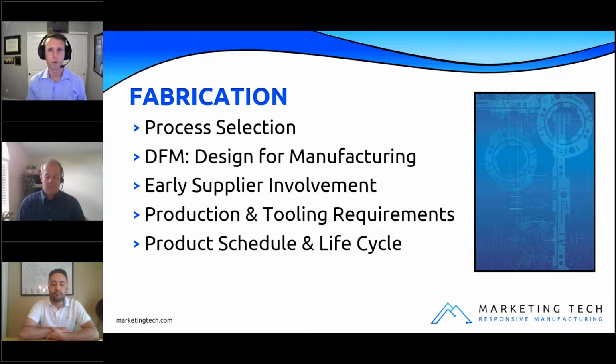If you were working on a consumer product, your product might be touched or adjusted or upgraded every 12 months. We talk about an iPhone as kind of the ubiquitous example. That's not the world that we're playing in here. Most of the medical devices that we support are intended to be in the field and in production for, I would say, a minimum of 10 years, often as high as 20 to 25 years. And so that changes your approach in terms of fabrication. You need to take those timeframes into consideration.